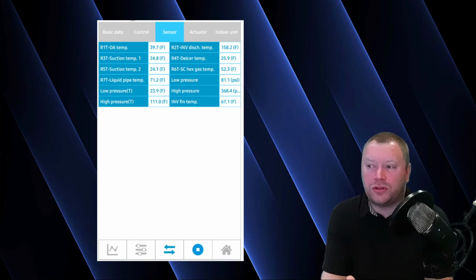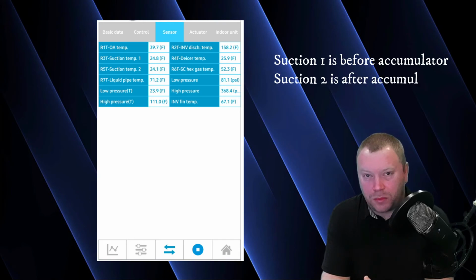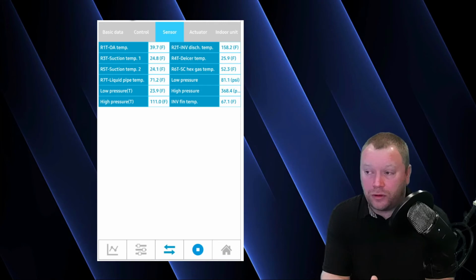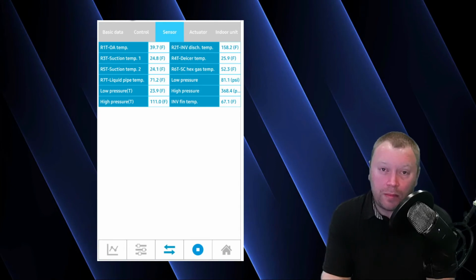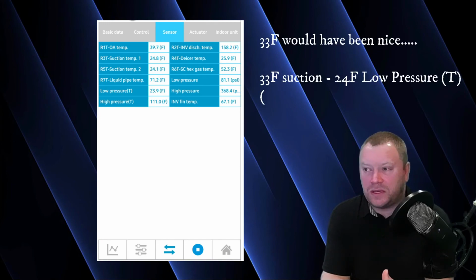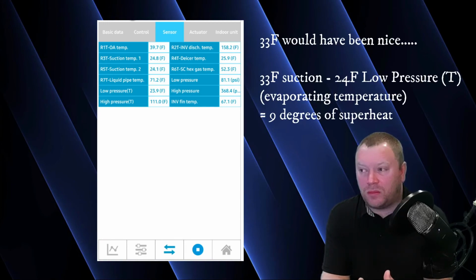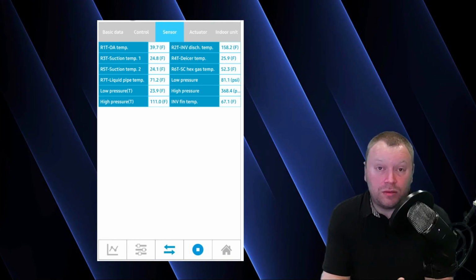Our suction temperatures, they're ultimately coming back to the compressor. There are two of them on this particular system because there's one before and one after the accumulator. They're both about 24 degrees. And then that low pressure gas is going to go back to the compressor. Now, this is not the best data that I grabbed a screenshot of at my outdoor unit. I would have liked to see my suction temperature be a little bit warmer, especially considering we're not operating that hard. So again, we're only 9 minutes into the recording.